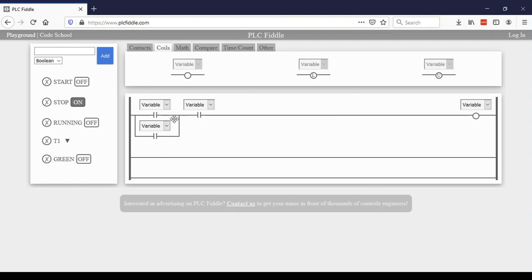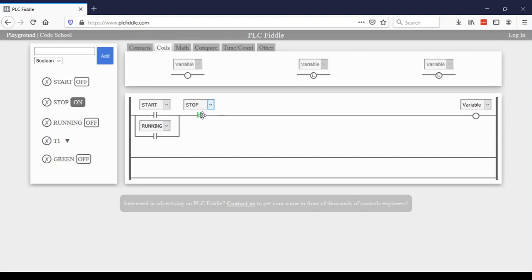So now that I have my first rung set up, I'm going to go through and say that when the start button is pressed or the machine is already running and the stop button is not pressed, then I want the machine to be running. So that is my first rung of the tree.